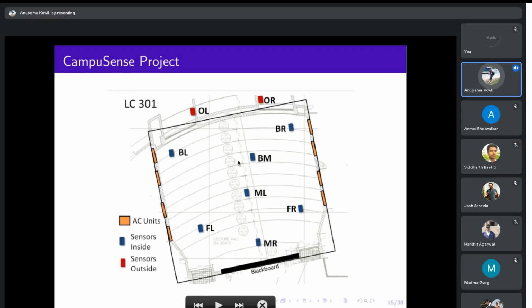This system is similar to the second architecture I discussed, where you regulate airflow into the room through fan speed control, and the fan speed control uses a proportional integral control logic to track the temperature set point by looking at internal conditions. Everybody follows this?